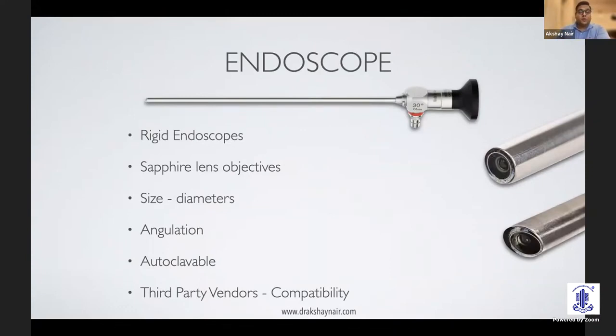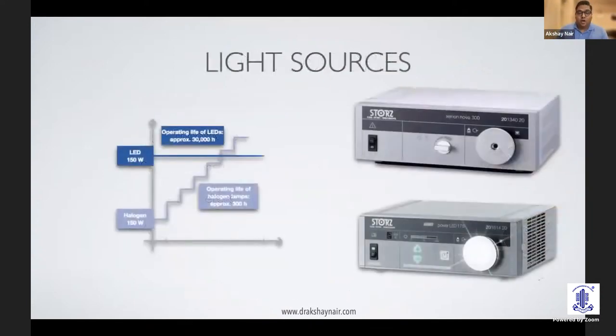And as is for most ophthalmic or any surgical equipment, you may also have third-party vendors which are compatible with a standard company. And they of course offer the equipment for a cheaper cost. So you should always check, especially if you're buying from a third-party vendor, whether it is compatible with your endoscopic handpiece, with your camera head or not.